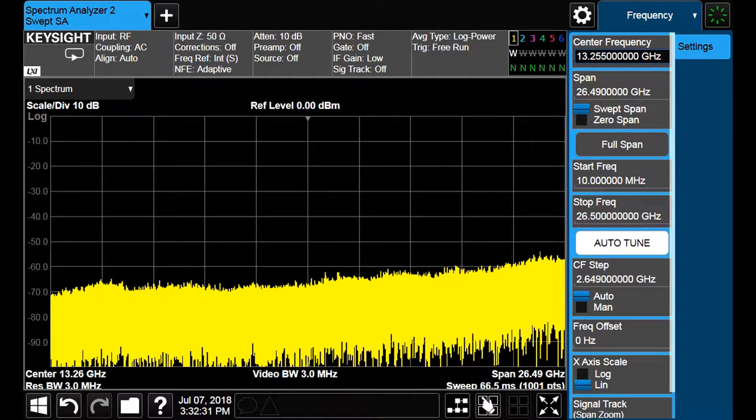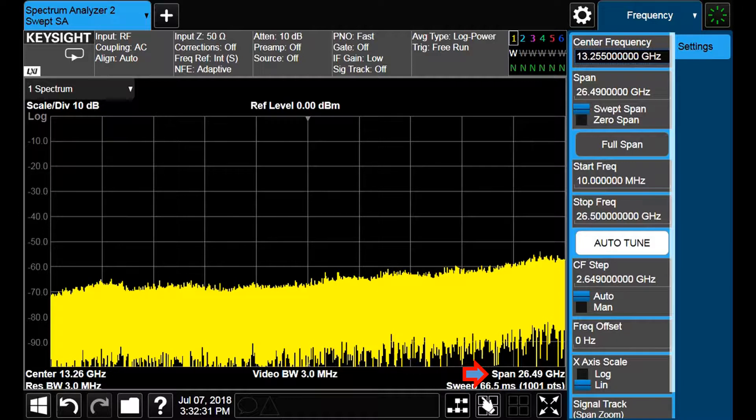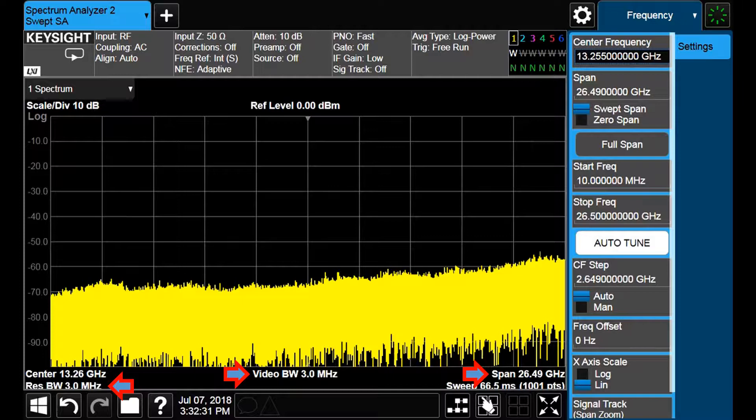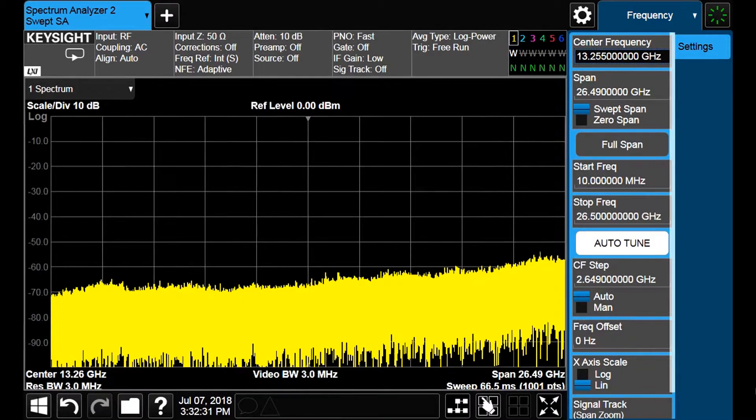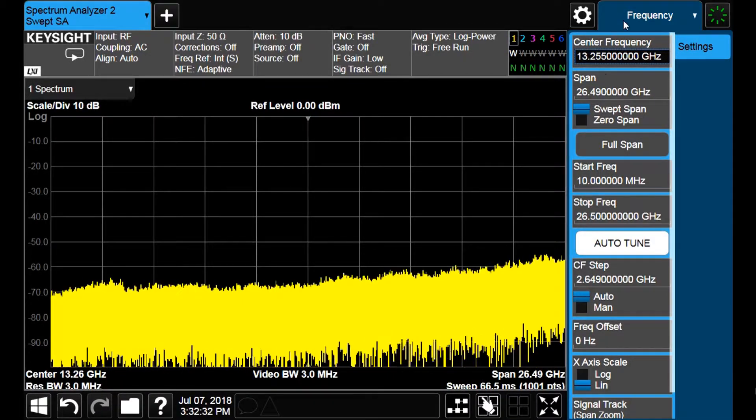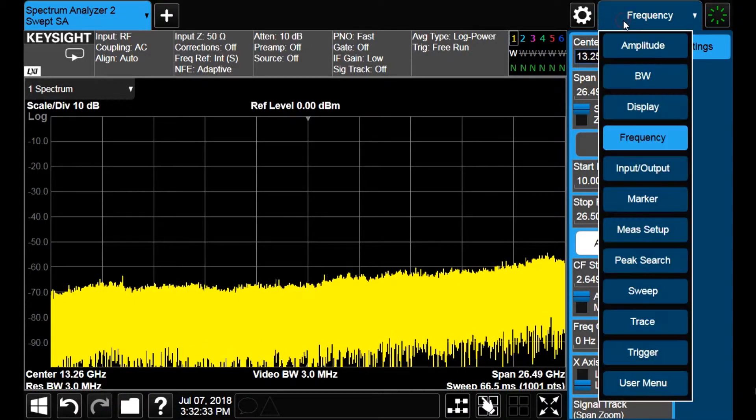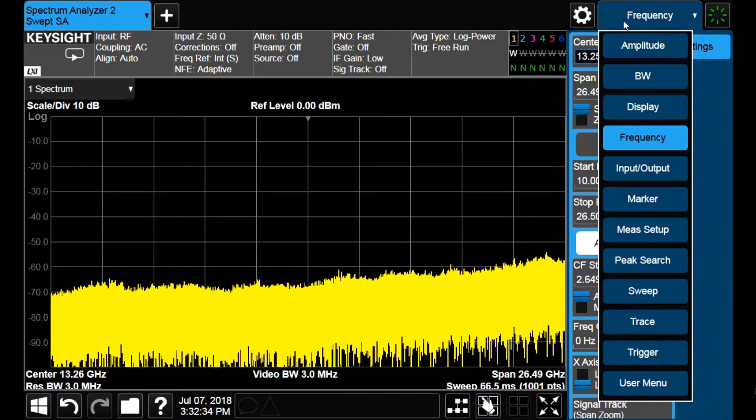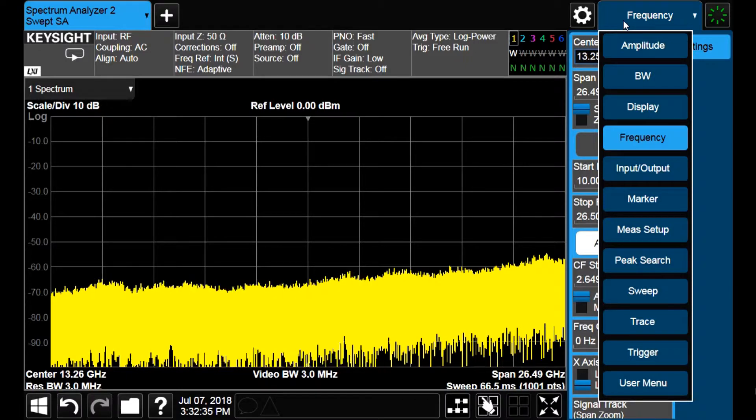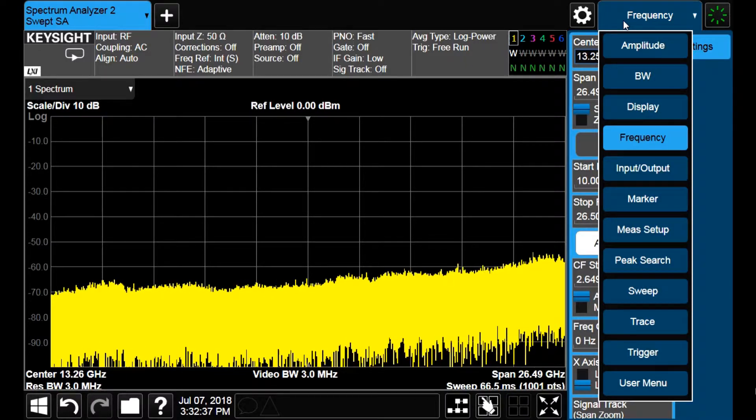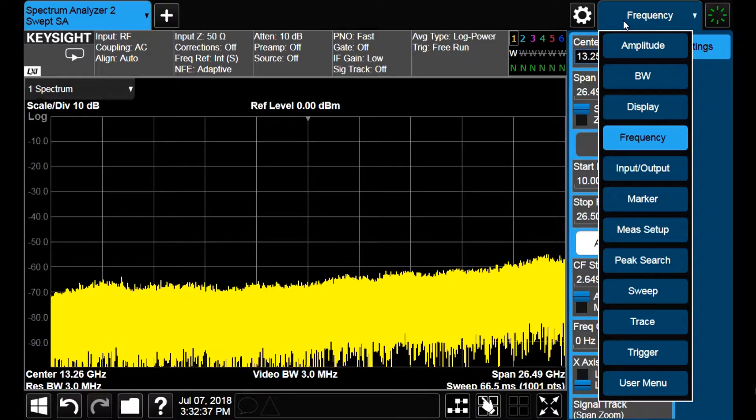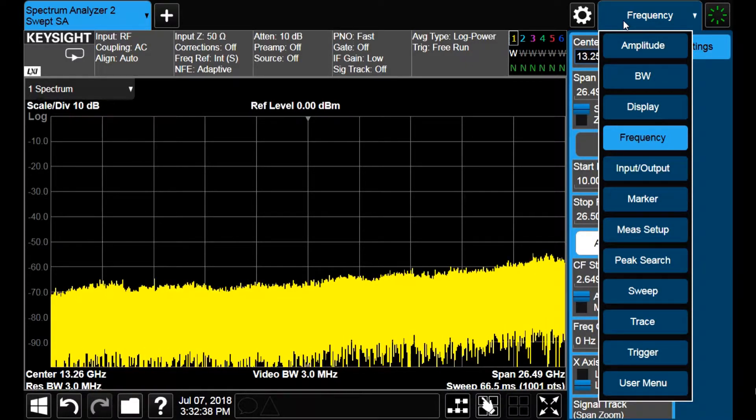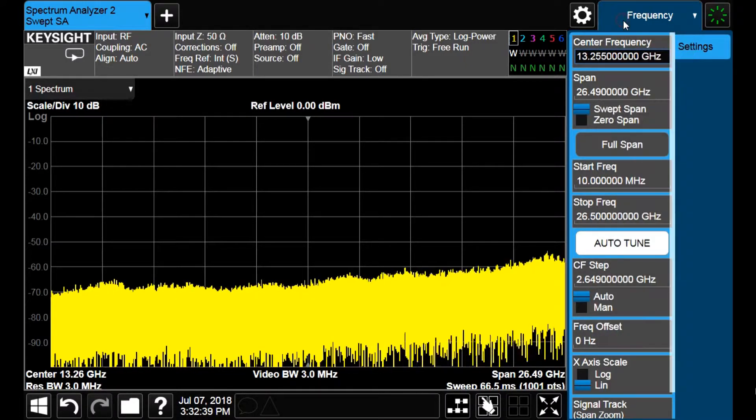In the default configuration, the instrument shows you a full span measurement with both resolution and video bandwidth equal to 3 MHz. If we tap on the drop-down menu we see the options to set amplitude scale, resolution bandwidth, display, frequency scale and some others.